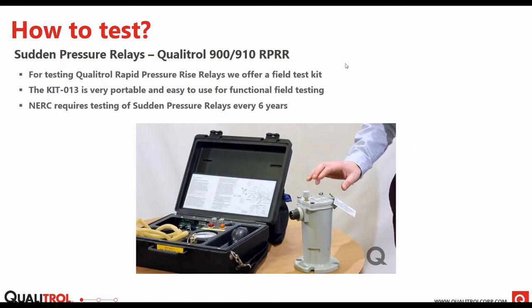Moving on to our sudden pressure relay, this would be our Qualitrol 900 or 910 RPRR, typically called. For field testing of these, this is a full functionality field test. It tests the function of the RPRR itself and the switch function. To do this, we have a field test kit, which is our Kit 013.